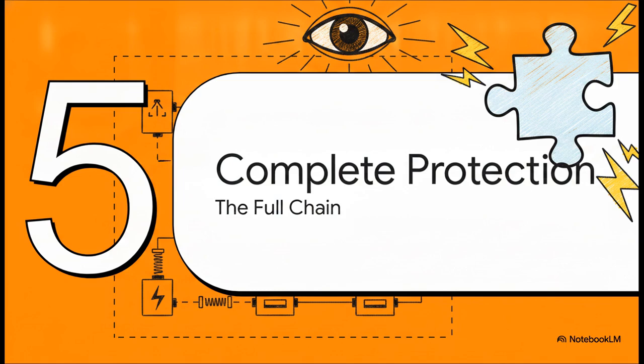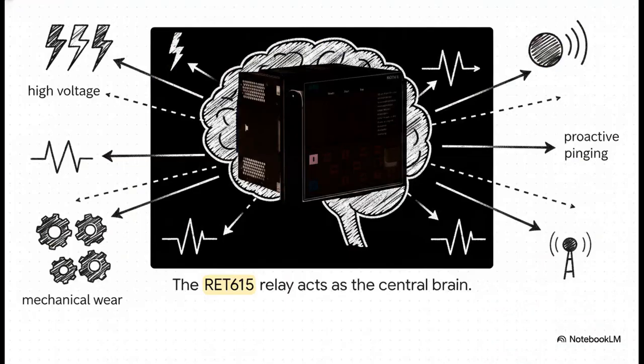The complete protection chain. Let's pull back and look at the big picture for a second, anchoring this all back to our actual hardware. By adding trip circuit supervision, we are slotting in the final critical piece of the local substation protection puzzle we've been building over these past few episodes. Take a look at the RET615 protection and control relay. This device is acting as the central brain synthesizing all these complex converging functions. It's reading the high voltages, crunching the differential algorithms, monitoring the mechanical wear and tear, and, as we now know, proactively pinging the external copper wiring, all from this single hub.